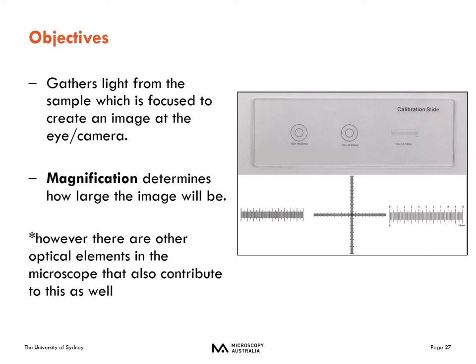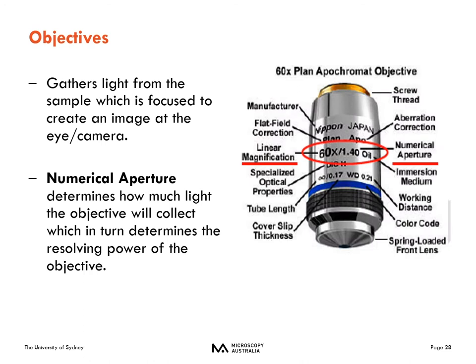Just because you're using a 60x lens with a 10x magnifier in front of your camera doesn't necessarily mean the final image is 600x — you really do need to do that calibration. The most important number on the objective is the numerical aperture. It determines how much light the objective collects, which in turn determines the resolving power, and in fluorescence microscopy, contributes to how bright your sample looks.